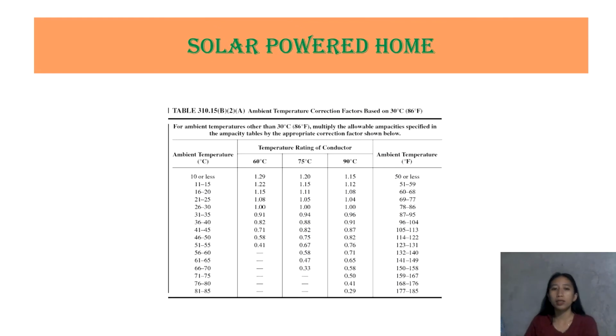Okay, so this is table 310.15, which is the ambient temperature correction factors based on 30 degrees Celsius. Dito makikita natin yung ambient temperature. So for the temperature rating of conductor, meron tayong 60 degrees, 75, and 90 degrees Celsius. And of course, the ambient temperature in degrees Fahrenheit.